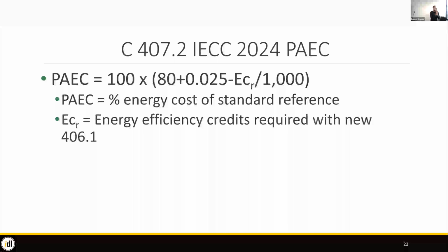2018, so just walking through again, just to help my own mind in terms of the linear nature of this. 2018, what we're doing right now, you've got 7 different options of efficiency. Pick one of them. Great. 2021, it's a points-based system based on the climate zone. 2024, it's a credit-based system based on climate zone and occupancy. And you have to have a certain number of credits, and those credits count into this formula for your total performance calculation. It's a bit roundabout.